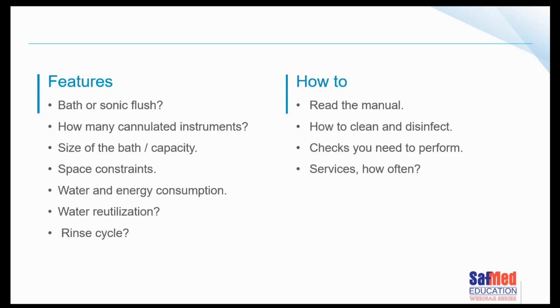So to use the ultrasonic cleaner, of course, you need to have read the manual, and you need a copy of the manual. Often we end up putting it somewhere, or it gets filed in maintenance or somebody's department, and nobody knows where the manual is. Please ask your supplier for a manual again if you don't have one. I'm sure they can give you one, because it's quite important to know how to clean them and how to disinfect them, and what checks you need to be performing on them, and how often you should service them.